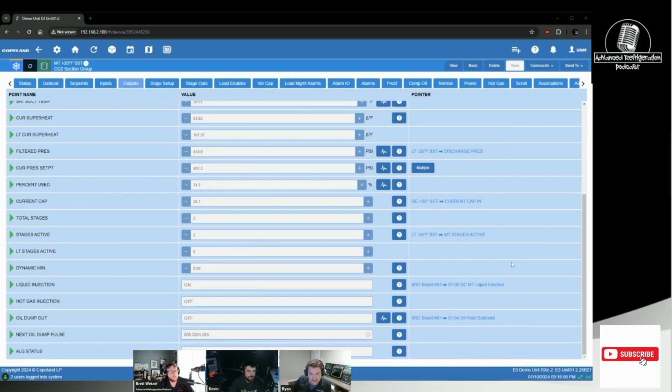I will say this: if you have EPRs, digital's all day long. If you have no EPRs, then variable speed. Also, if you have the service talent for frequency drives, there's definitely a fit for drives. I find if you're more in a remote area, digitals are quite a bit easier to troubleshoot. That's usually my big divide on choosing one or the other. But frequency drives are just fun.